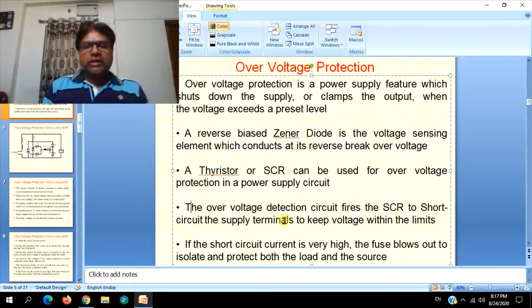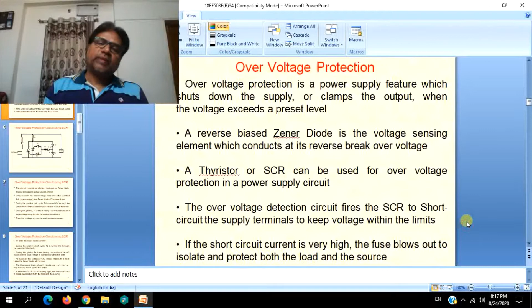The concept of overvoltage protection lies in this, that is, the overvoltage detection circuit comprising a Zener diode fires the SCR to short circuit the supply terminals to keep the voltage within the specified limits. In some specified cases, when the short circuit current is very high, the fuse blows out to isolate and protect both the load and the source. That is for crowbar circuits.